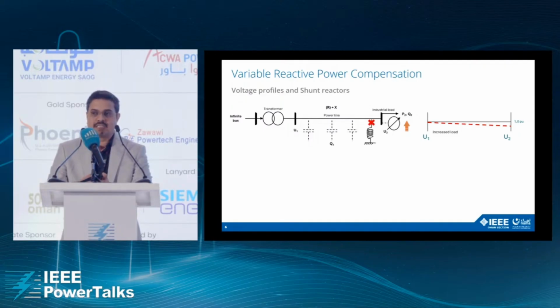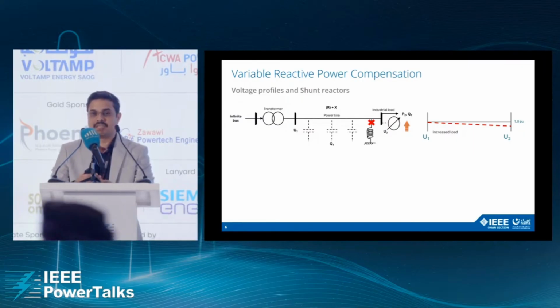The easy solution we can think of is that, when we have this imbalance or overcompensation, we can simply remove the shunt reactor from the network. But this calls for two different challenges. One, you need to have a complex network system. You need bigger circuit breakers which can disconnect the shunt reactor. And second, most important, while you're disconnecting a reactor of significant MVAR from the network, you're actually creating turbulence or transients in the network, because you are creating a big imbalance with a sudden disconnection by the circuit breakers.